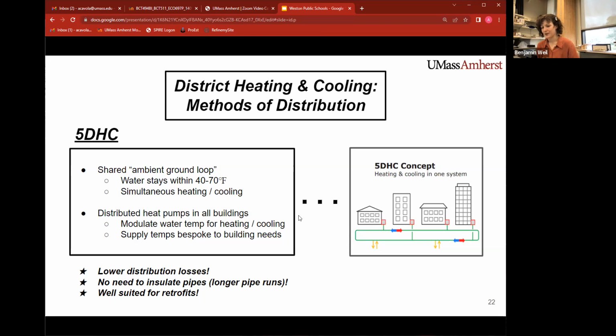And advantages of this configuration is that since the water in the loop is basically the same temperature as the ground, there's lower distribution losses, and you can have uninsulated pipe runs and longer pipe runs without worrying about distribution losses. You can effectively share heat resources between buildings, move heat from where you don't need it to where you do need it if you have simultaneous heating and cooling loads. And you can tailor the supply water temperature to each building's individual existing distribution system. Some disadvantages of this is that there's more moving parts because each building has an individual heat pump. And also, since the distribution system is designed for ambient temperature supply water, it's hard to integrate backup or supplementary heating supplies like a boiler because you would be experiencing distribution losses.